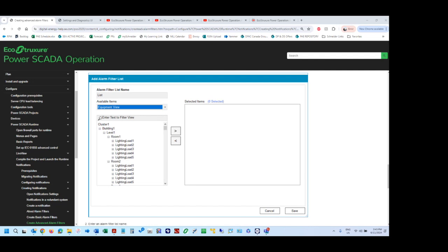So that'll be an interesting one to see how that's done, because I'm not exactly sure how it all ties together, since it seems we have two different systems here. We've got the PME and we've got the EPO, and somehow the alarms work together. That part I can't wrap my head around. Well, EPO is running the alarm server and the alarm engine, but we're taking tags from the meters that are ION meters, and we're taking tags from the RTAC, right? I'm just curious. If I set up the set point alarm in Designer, because that's my easy way of doing it, it hasn't existed yet. The alarm has never been launched. It's just sitting there waiting to launch. So how does EPO know that it exists?